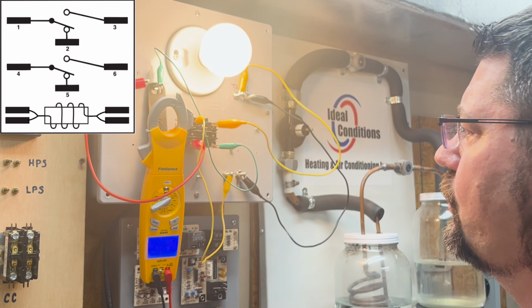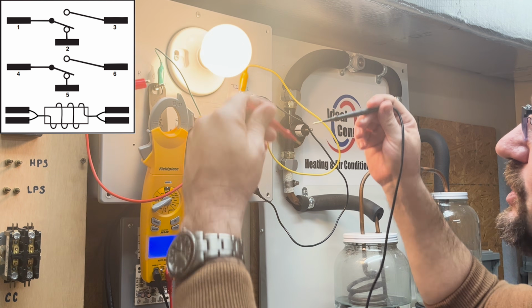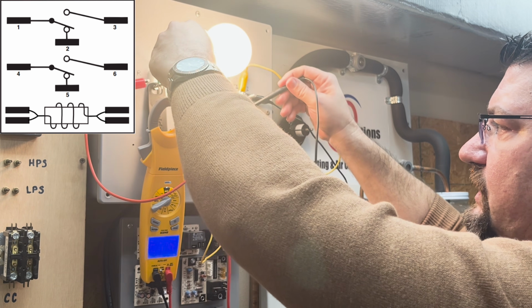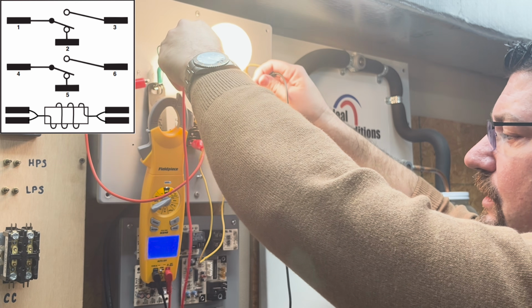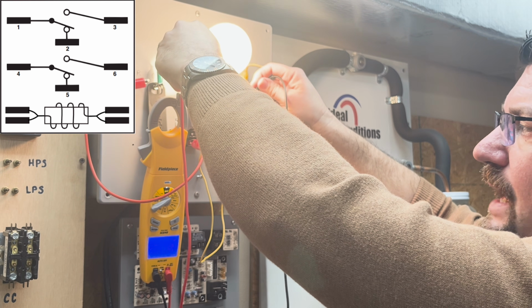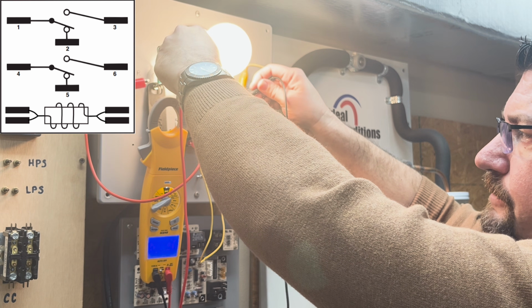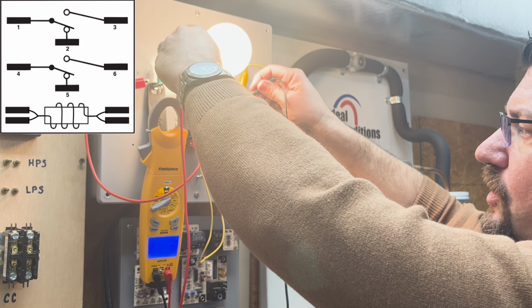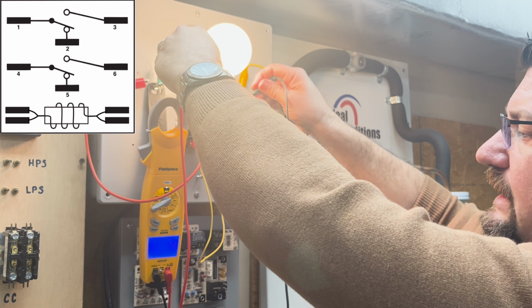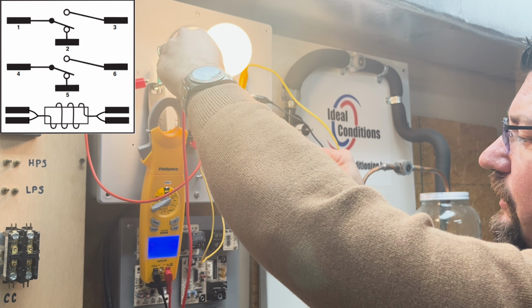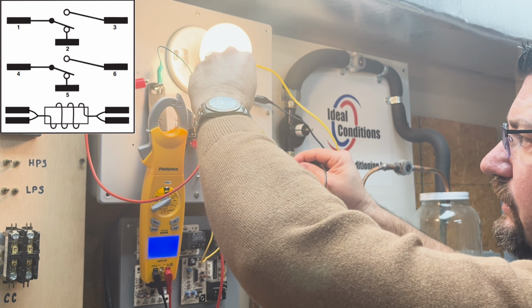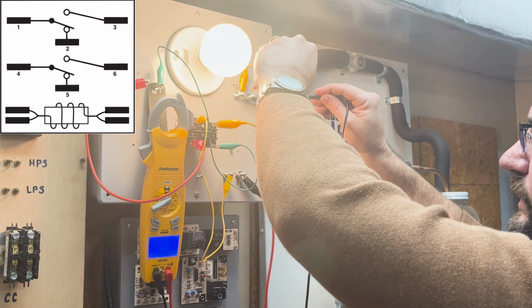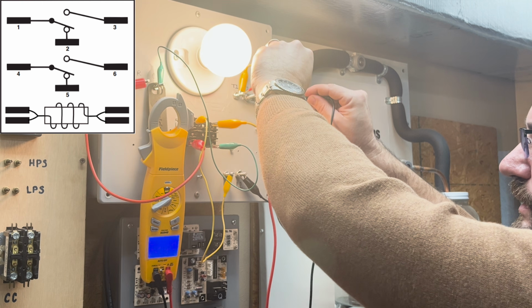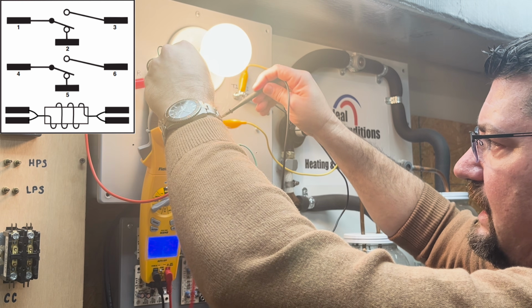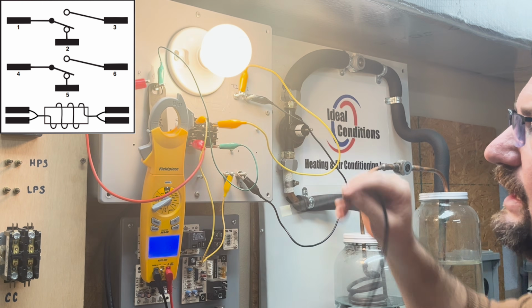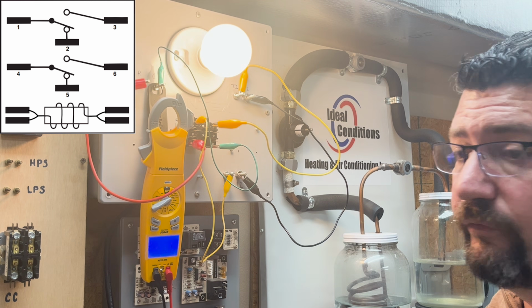which will force the load on. And you're now going to realize that we read 0 volts, even though we know there's power there. There's L1 present on both sides. And because we can't read a difference of anything like we could if we did this, okay, or this, or this, because we don't read anything here, that means it's the same leg of power. Doesn't mean that 0 means no voltage.